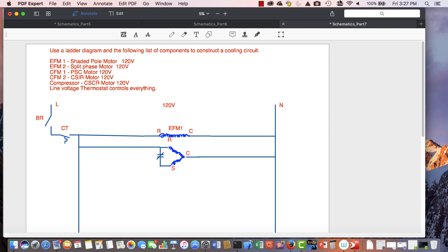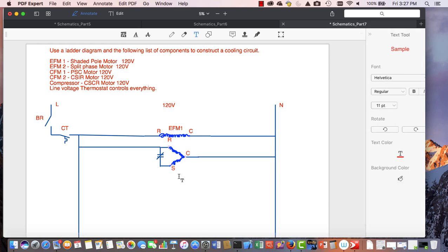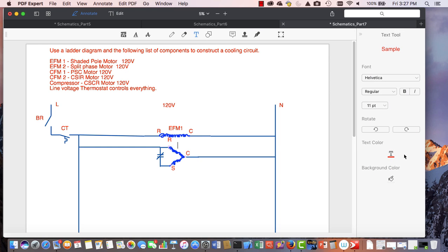Okay, let's label that because that has to be EFM2. So now I have my split phase motor, EFM2. And that's a centrifugal switch. No start components on that other than that switch. That switch will open when the motor reaches about 75% of its rated RPM.